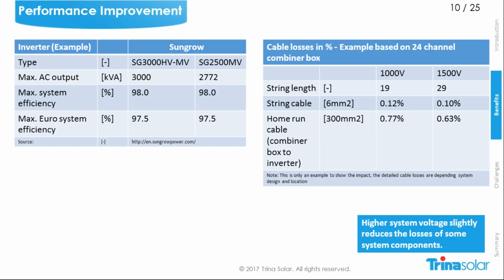For the cabling losses, for the cable sizing, this can be calculated. I have calculated it here on the right side. If you compare the 1000 volt system with the 1500 volt system with the same cable cross section, you can see that the cable loss gets reduced. In the string cable case it's quite small, but it's still there. And for the home run wire, it's approximately 0.14%. That means you have additional energy that you can feed into the grid. Even if it's slight, every penny counts. You can increase your energy yield and your profit and reduce your levelized cost of energy.